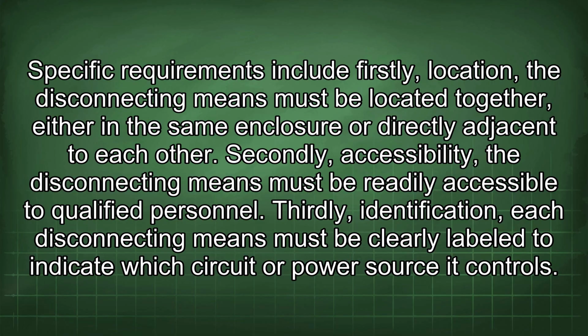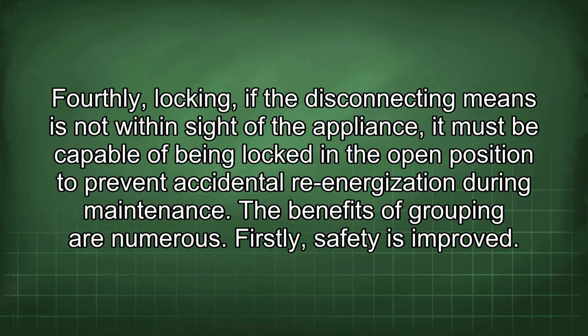Thirdly, identification. Each disconnecting means must be clearly labeled to indicate which circuit or power source it controls. Fourthly, locking. If the disconnecting means is not within sight of the appliance, it must be capable of being locked in the open position to prevent accidental re-energization during maintenance.